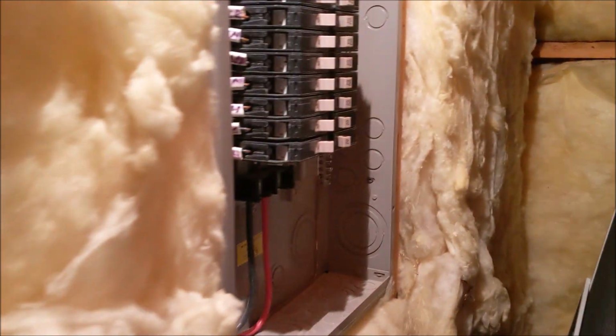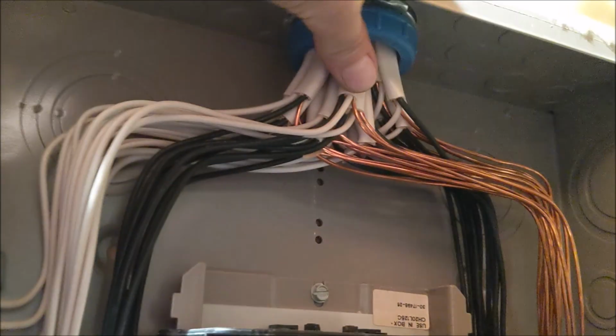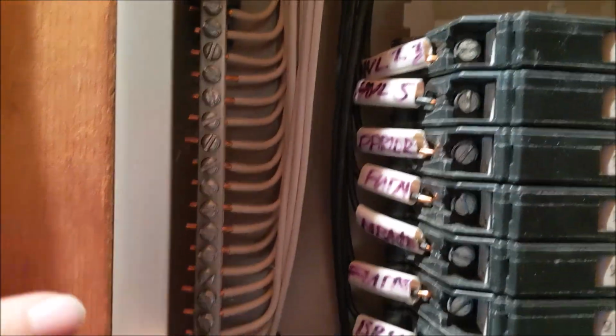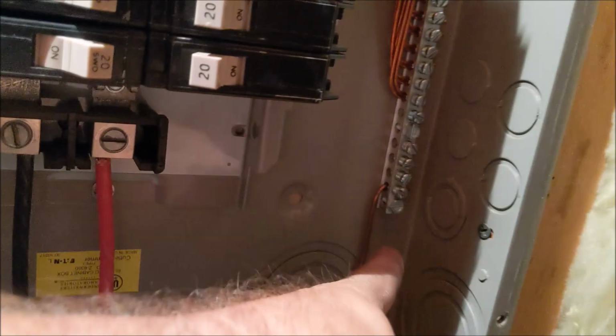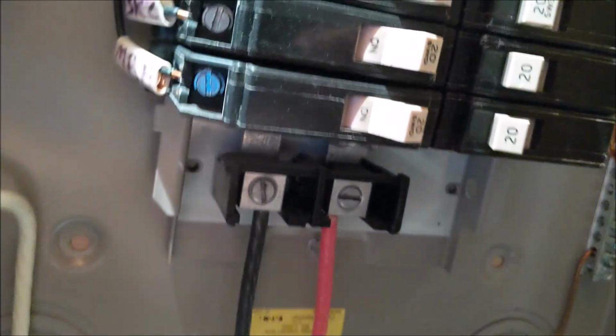All right, we're still in the attic, right off the stairs, and this is that Cutler Hammer panel open. So basically we have all the branch lines coming in. We have all the neutrals here that are isolated from the panel. I wish I could back this thing up a little bit. Then we have all the grounds here that are bonded to the metal frame. These are the two hots coming in, feeding the main panel, and everything's labeled.